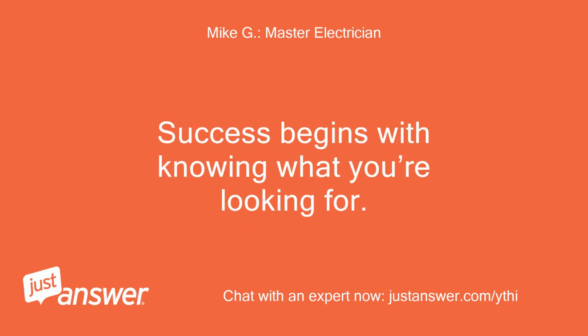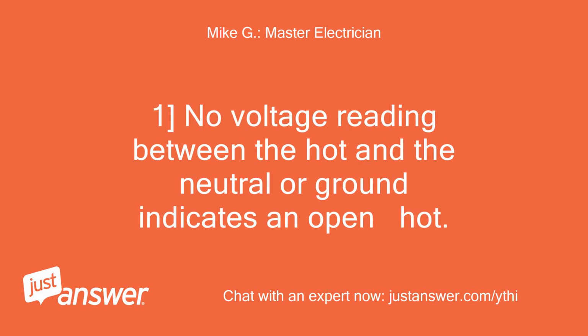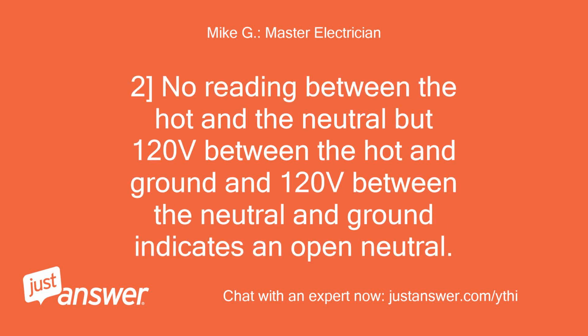Success begins with knowing what you're looking for. 1. No voltage reading between the hot and the neutral or ground indicates an open hot. 2. No reading between the hot and the neutral, but 120 volts between the hot and ground and 120 volts between the neutral and ground indicates an open neutral.